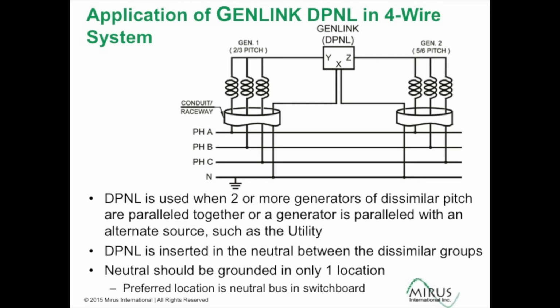And the other thing that's important is that the system should be grounded in only one location. Here we're showing the ground to be at the neutral bus in the switchboard. If we don't want to ground it here, we can also ground it at the X terminal of the DPNL. But it should only be grounded in one location so that we only have one return path for fault currents.